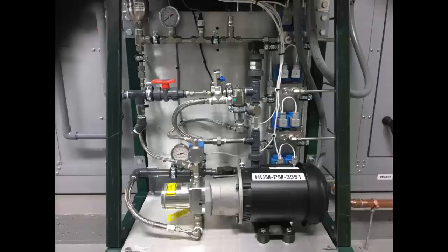But what would happen if one of them fails? Well, how could they fail? They could fail in a couple of different ways. As I pointed out earlier, it's actually one valve. Let's restate that: it's one stainless steel block, and actually it's right down there, but it has two valves in it. So there are two valves doing two different purposes. You could have one that may fail or another one that may fail, or both of them could fail.